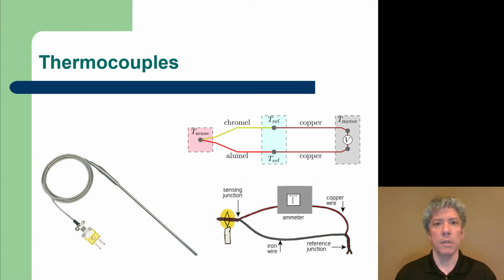Now, for practical purposes, we don't typically just have two dissimilar wires that are connected to either end. Rather, we connect the thermocouple, which is the two dissimilar wires, at one end, at the sense end, you see that in the pink box on the left in the upper figure, and then connect it to sensing equipment, which will have its own types of wires. For example, copper. Copper is a fairly common wire. Now, since there's a dissimilar metal between the chromel and copper junction and a dissimilar metal between the alumel and copper connection, those junctions also generate their own millivolt signals.